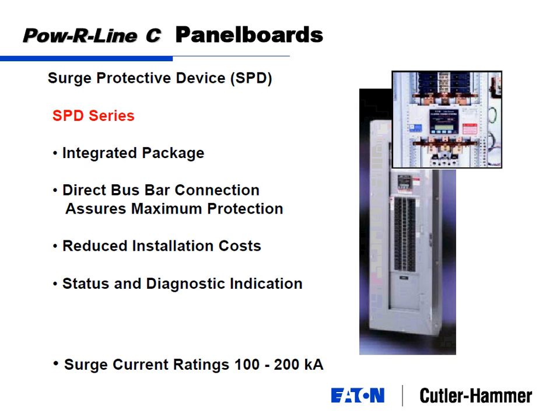For each inch of cable between your SPD device and your bus, the let-through voltage increases by about 20 volts. So if you add 20 inches of cable to feed, say instead of mounting this here in the chassis, right there on the chassis with little bus connectors straight to the A, B, and C phase, you take that device and you mount it alongside of it here and run cable from the panelboard over to there, 20 inches of cable is going to increase your let through voltage by about 400 volts.